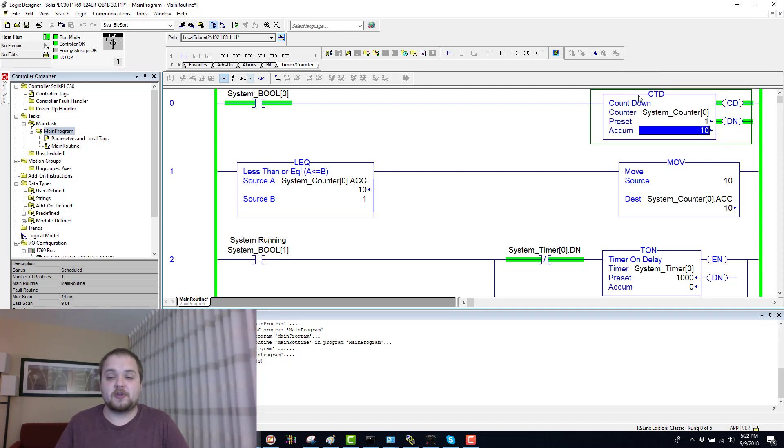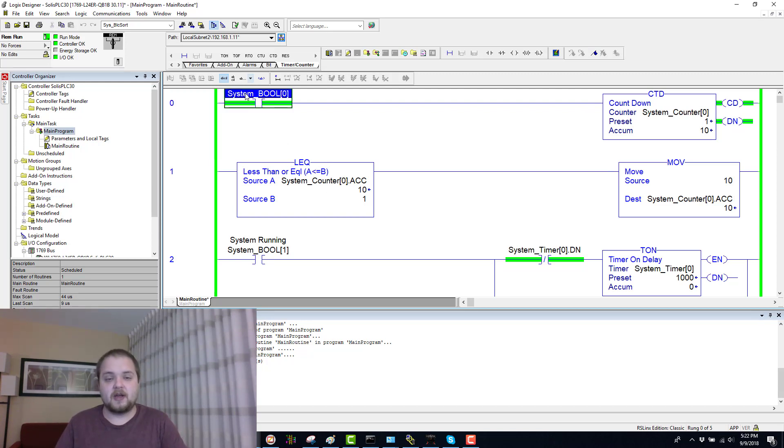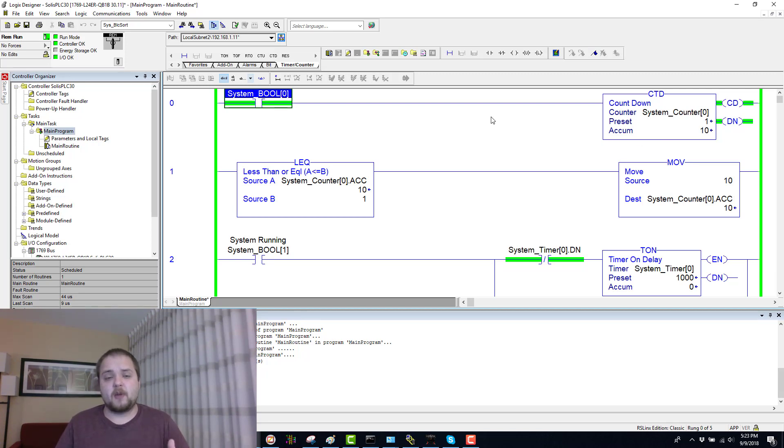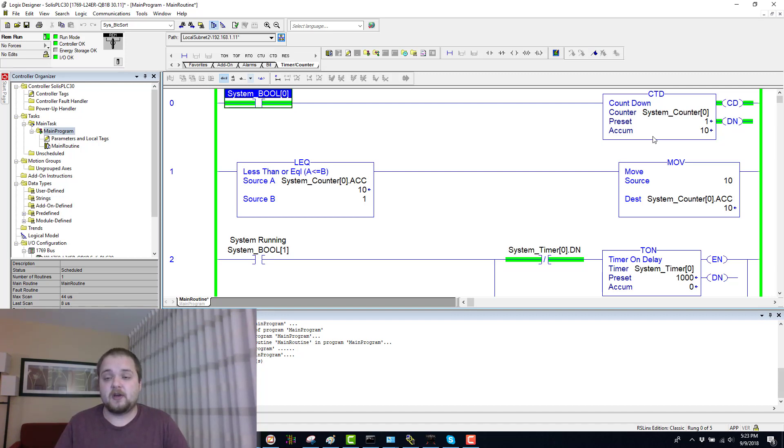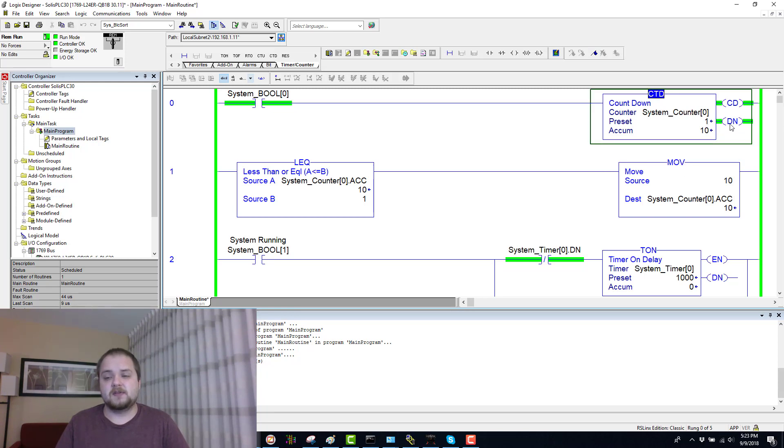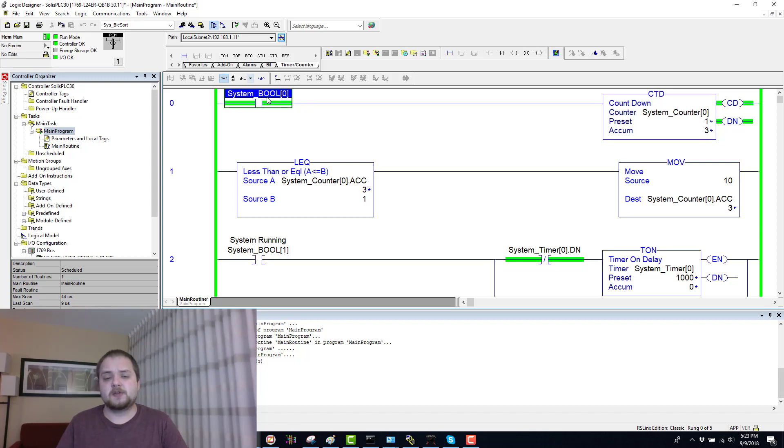Very cool. This is used in, I've seen this used in this fashion before, where you have something which counts down but then there's a move instruction which executes the actual reset of the counter. If you do not remember, in the previous video I've used a reset instruction in order to reset the counter. Now here it's a little bit different, I'm doing a move. This also means that the done bit, do notice that the done bit never actually unlatches.